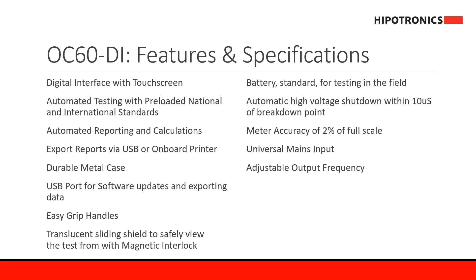If you slide open the shield, the high voltage of the OC60 DI will automatically stop. The system now comes with a battery included, which allows for on-site testing. There is also an automatic high voltage shutdown within 10 microseconds of the breakdown point. The system's accuracy is 2% of full scale, and it has universal mains inputs which allow for adjustable output frequency.